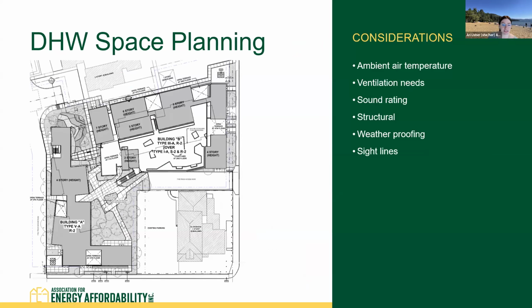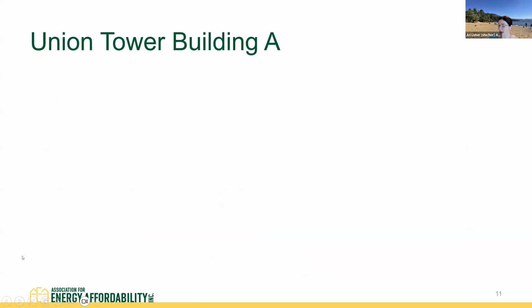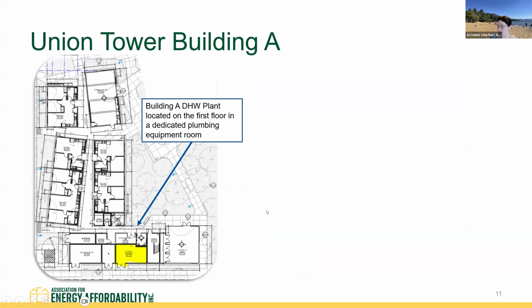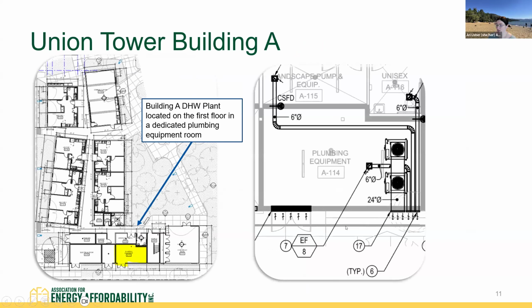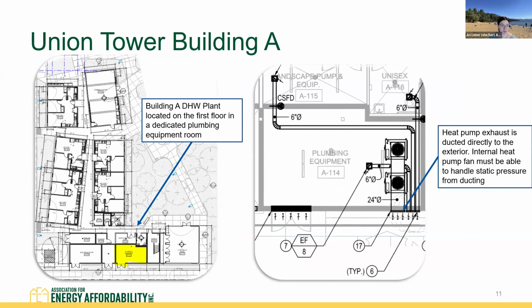All right, so now let's really take a look at Union Tower. Building A, the plant is located on the first floor in a dedicated plumbing equipment room. And what happens in this case in an enclosed space is ventilation becomes really important because heat pumps do exhaust cold air, and without ventilation, the heat resources in the space can become depleted, and the efficiency of the heat pumps can really become degraded. So what we're seeing here is a great design.